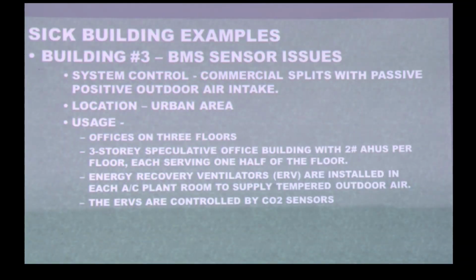Third one, BMS sensor issues. This one I like. This was a building that was designed by an engineer, and it's basically what I consider the incorrect application of technology. So it's a three-story office building. It's got energy recovery ventilators in the plant room, which is supposed to ensure that the air that's brought in is exchanging energy with the exhaust air. So you're bringing in tempered air. And these ERVs are controlled by CO2 sensors.